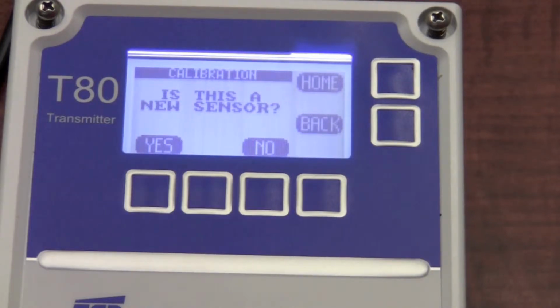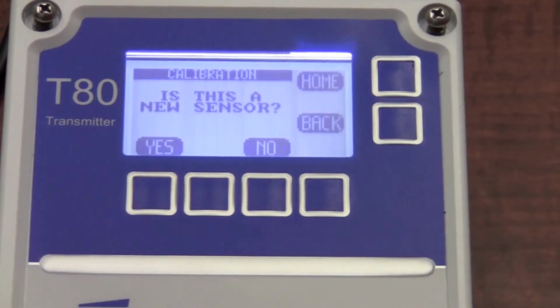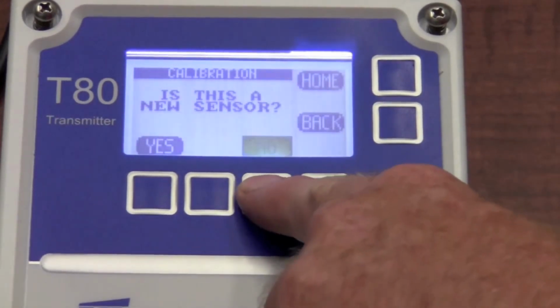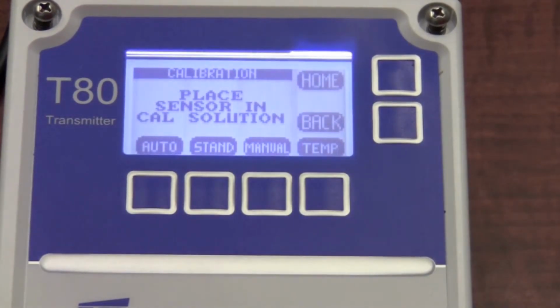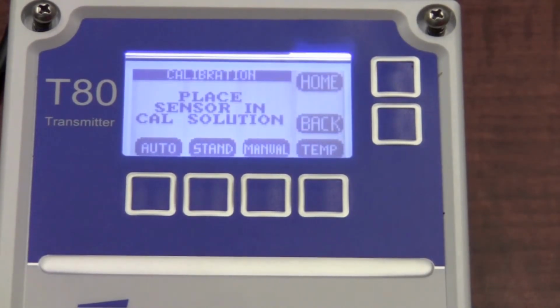In our particular case, this probe is not brand new, so I'm going to answer no. If I answer yes, it wipes out all 3 calibrations and would accept the one that I'm going to perform as the one and only. The T80 simply asked me to place the sensor in one of my calibration solutions.